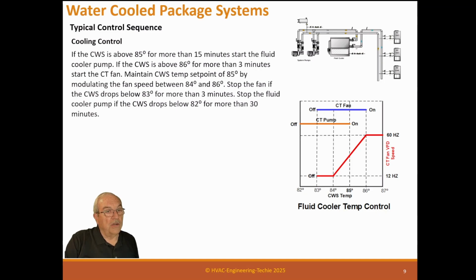But while it's on, it will modulate depending upon the temperature between 60 hertz and 12 hertz, which is minimum. I mean, you probably could go to 10 hertz, but not much lower than that. So this is the speed. It's going to ramp the speed up and down, trying to maintain this 85 degree temperature set point. So if it's over it, it'll go full speed. If it's under it, it'll go below. This is just a temperature cooling diagram.